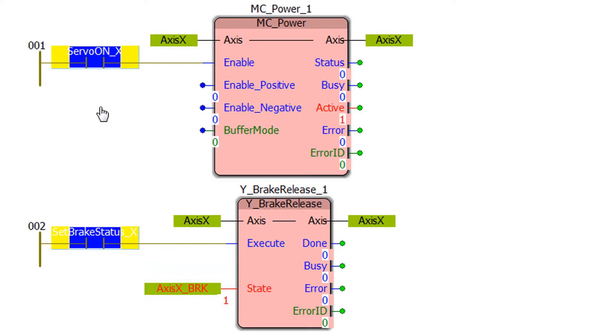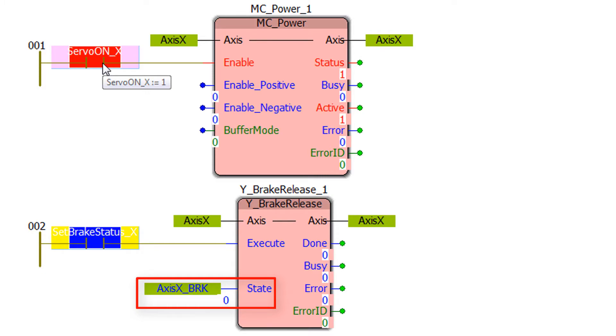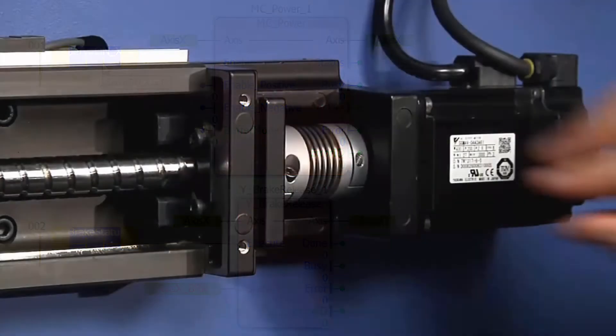Under normal operation the brake output turns on and off as the servo turns on and off. Servo on, the brake is off or released. Servo off and the brake is engaged.